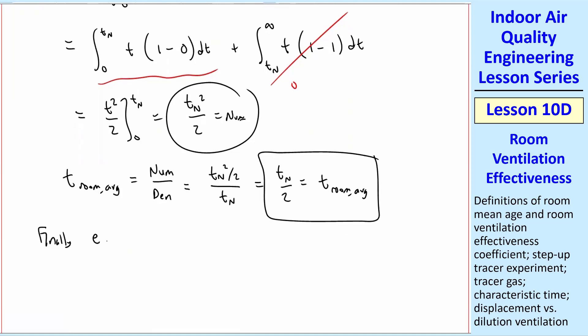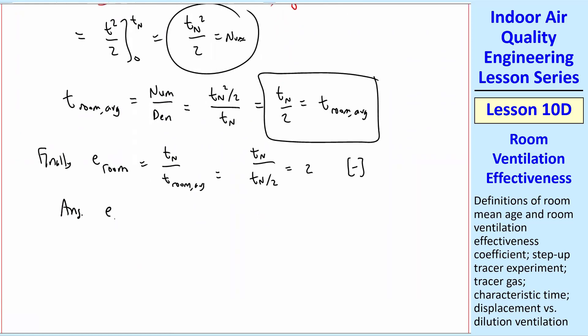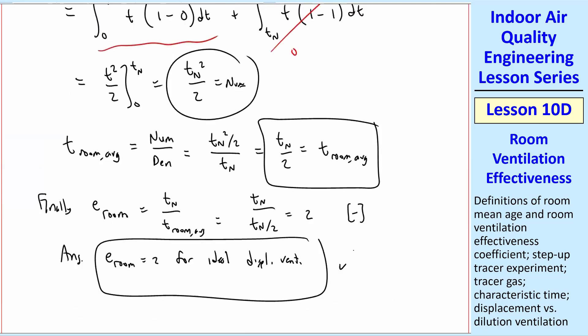And then finally, what we really want is E room TN over T room average equal TN over TN over 2, which is what we just found, and that gives you 2. And that's unitless, there's no dimensions, it's just a ratio of times. So our answer is E room equal 2 for ideal displacement ventilation, and that agrees with what I had written. E room is 2 for ideal displacement ventilation. So we've just kind of double-checked that with all this math.